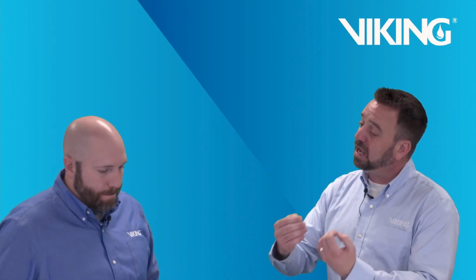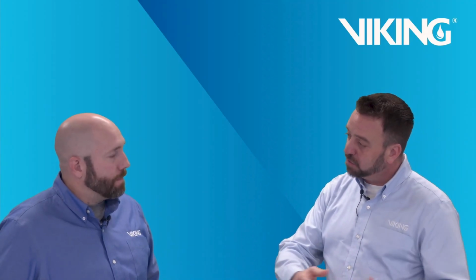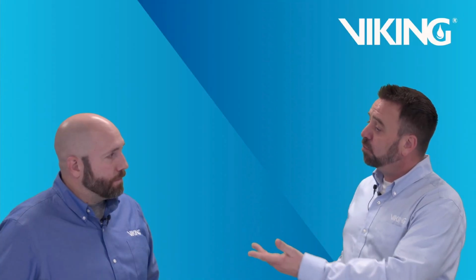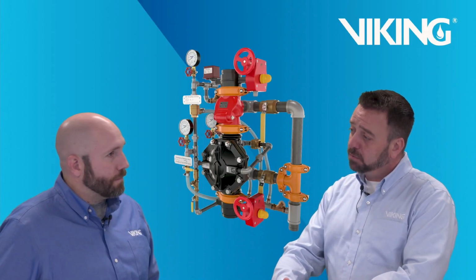Also, on top of that, the 30% increase in the design area. Okay. So dry systems require a 30% increase in the remote area. Double interlock pre-action systems require that same 30% increase in the remote area. So actually what we offer is what we call our dry to pre-action upgradable system.